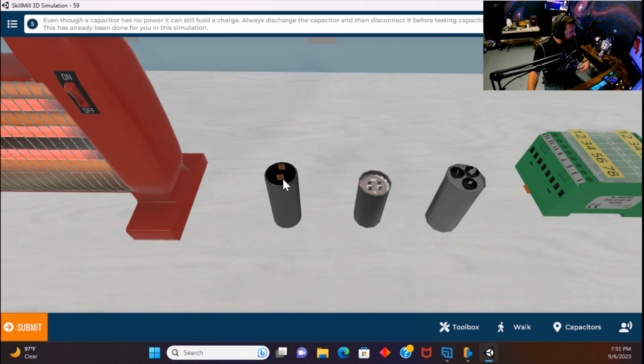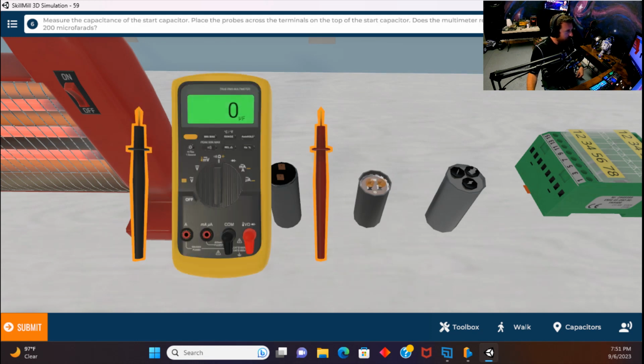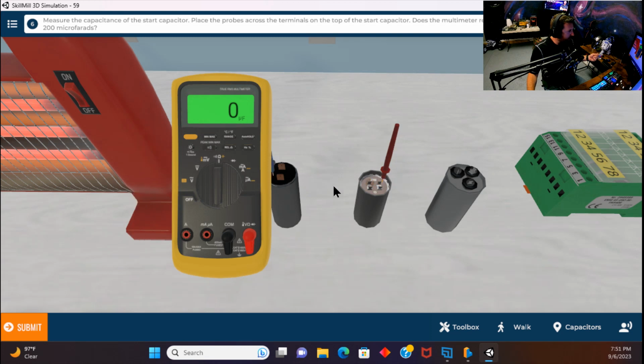So now it's saying, even though a capacitor has no power, it can still hold a charge. Always discharge the capacitor and then disconnect it before testing capacitance. This has already been done for you in this simulation. Okay. Now it's telling me, measure the capacitance on the start capacitor. Place the probe across terminals on top of the start capacitor. Does the multimeter read 200 microfarads? So let's take our red lead, put it on there. Take our black lead, put it on there. Does it read 200 microfarads?